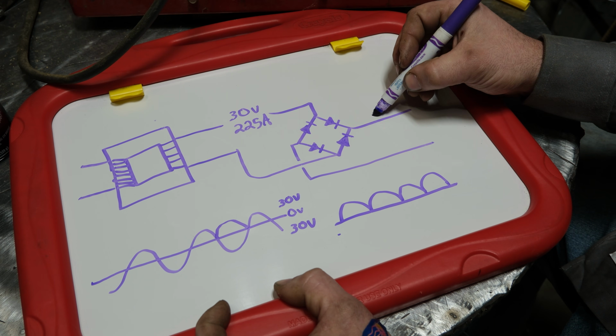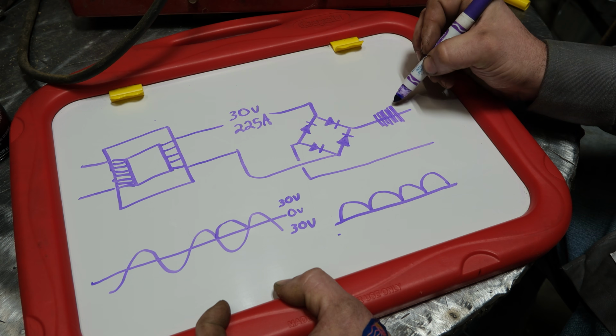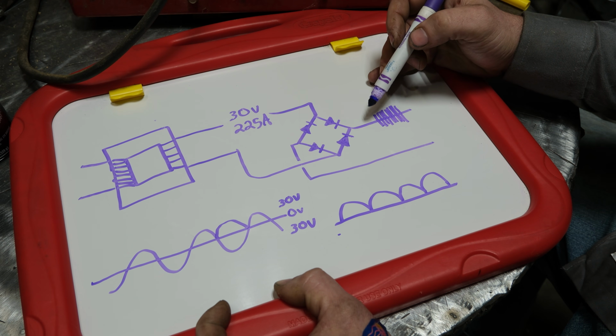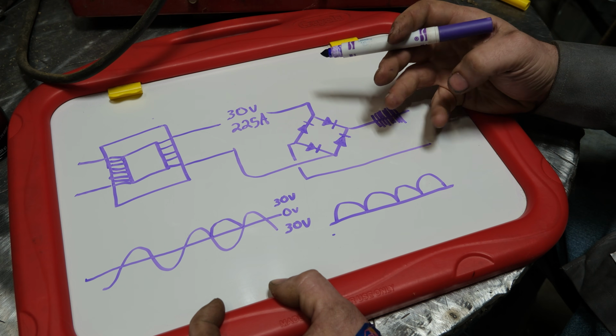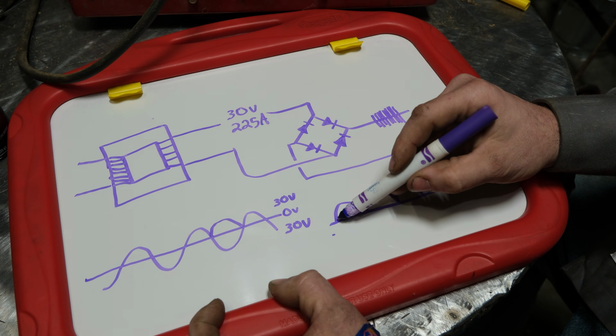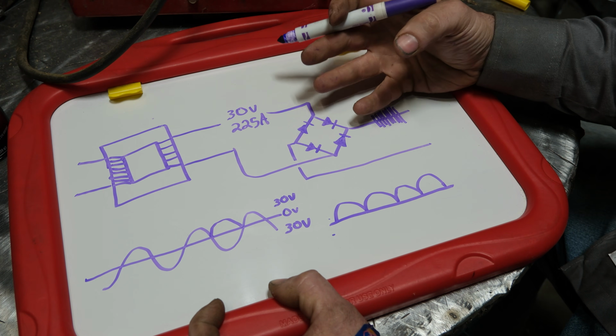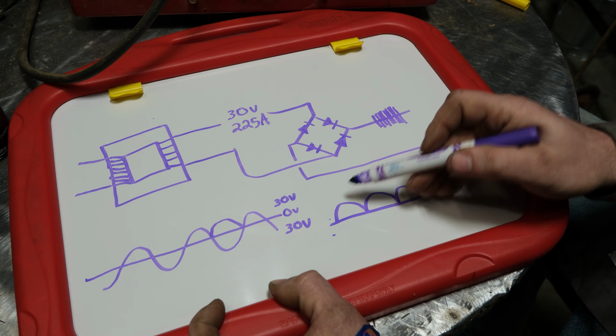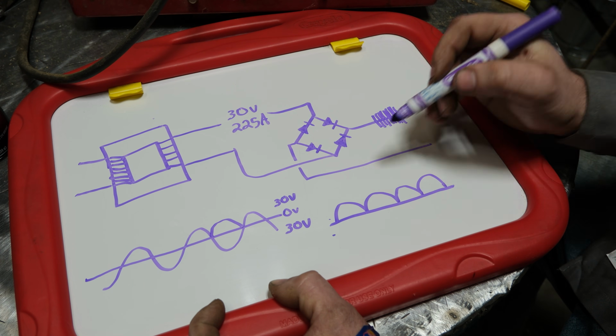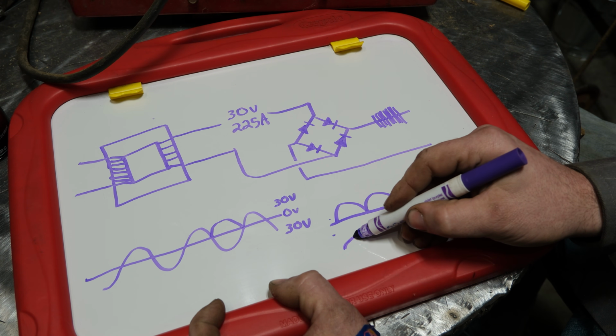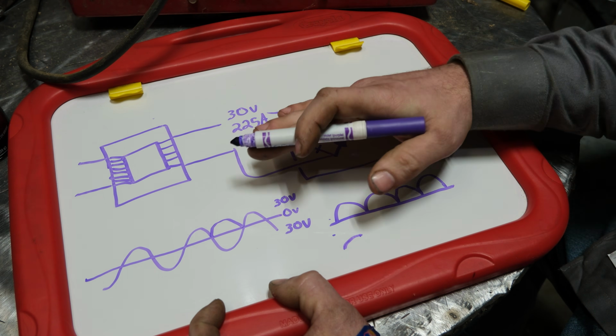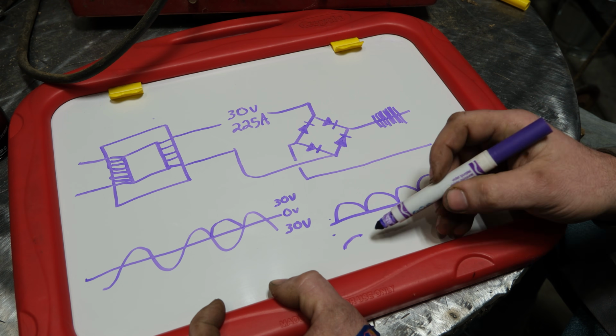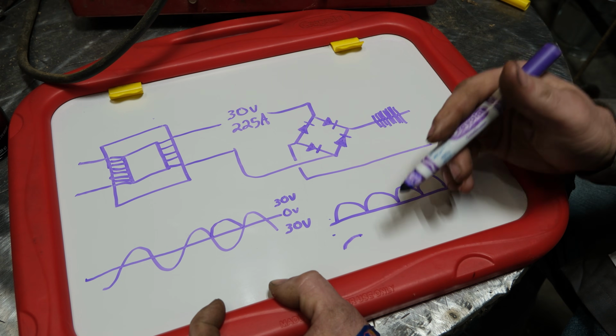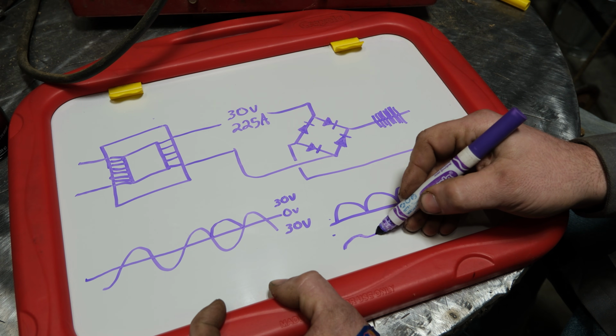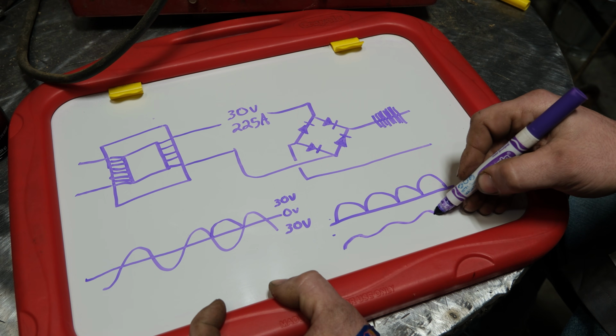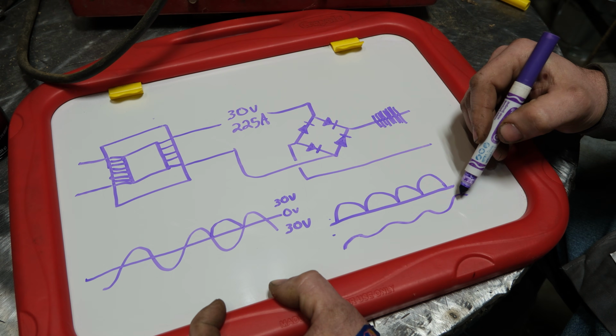That big coil of wire that looks like a transformer, placed on the output of the bridge rectifier, functions as a choke. It more or less resists changes in voltage. As the voltage comes up, that big mass of copper resists it, so the peak voltage is less—it's pumping the brakes on the voltage rise. Then as it drops off, it's stepping on the gas, resisting the change of voltage. So that reactor, or choke, creates a smoother ripple.